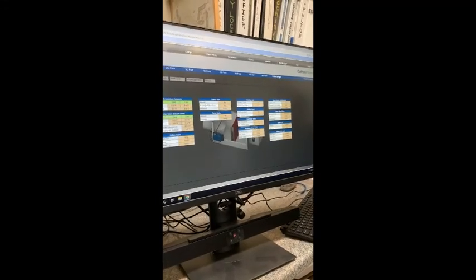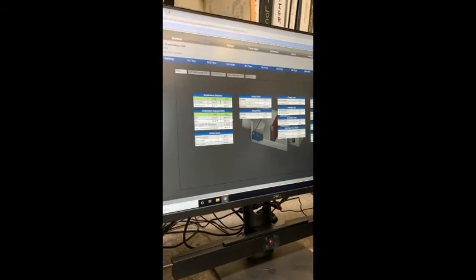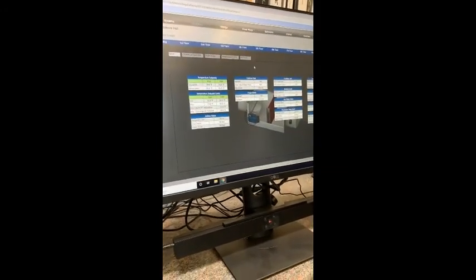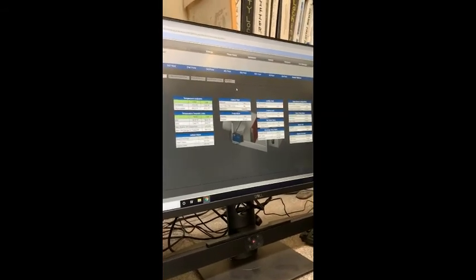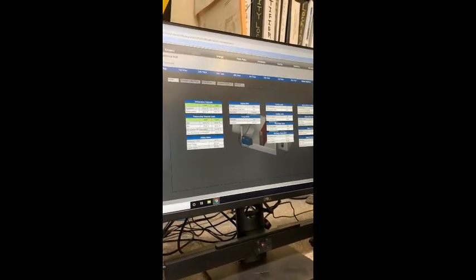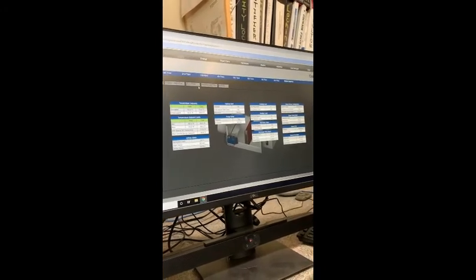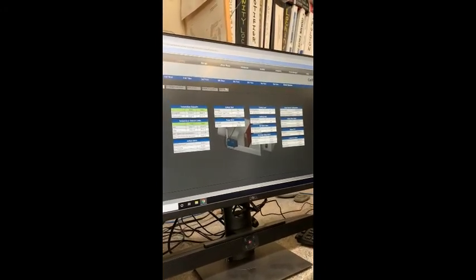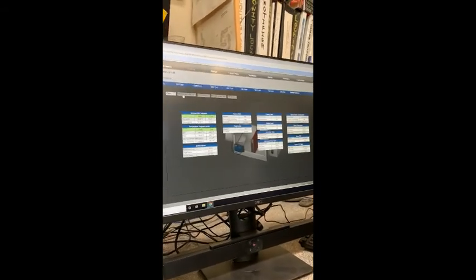Each building does also have global settings, where if you set these values here, it would then set it everywhere for every one of those. Right now this is for every VAV. If we changed every VAV, not the air handlers, because the air handlers are so individual, they're basically one-offs. But these are more at the zone level.